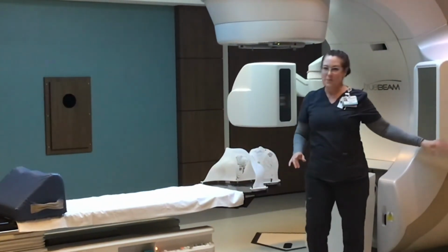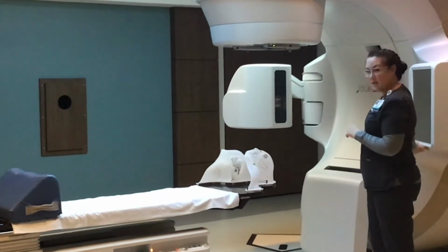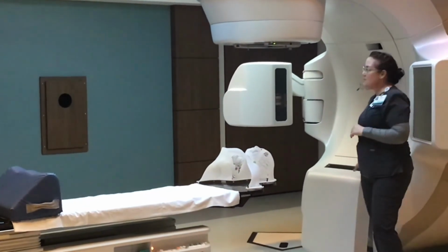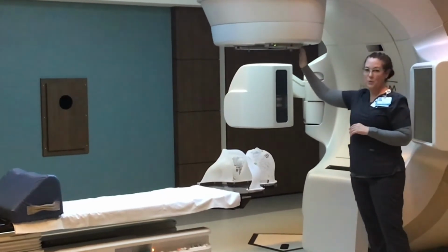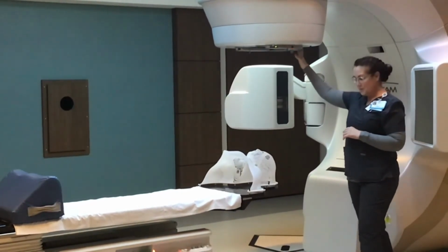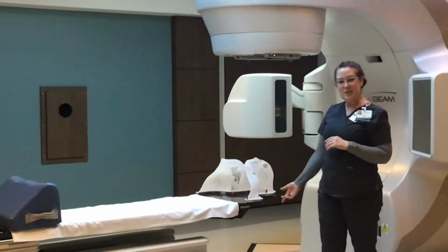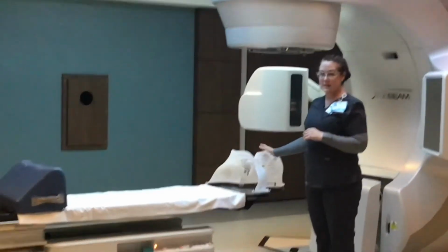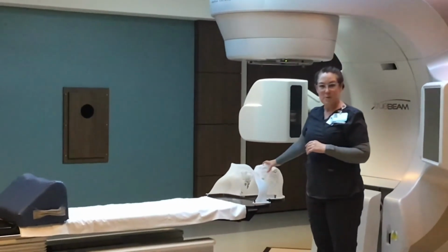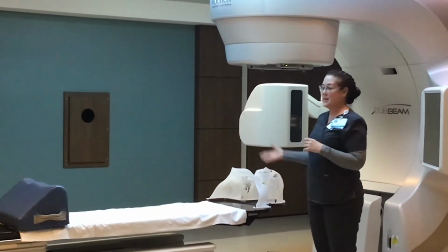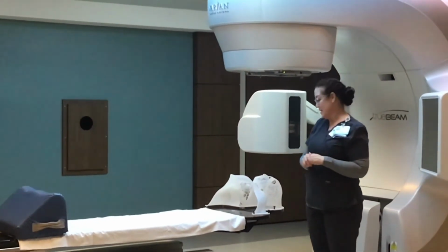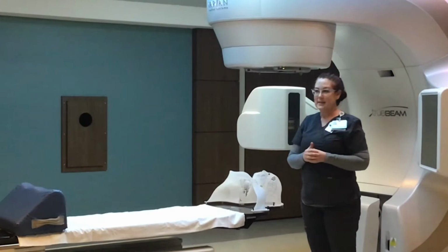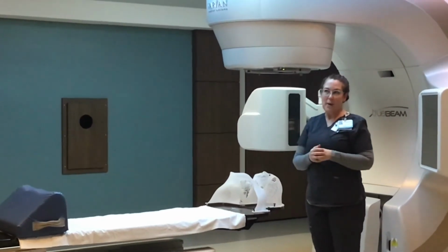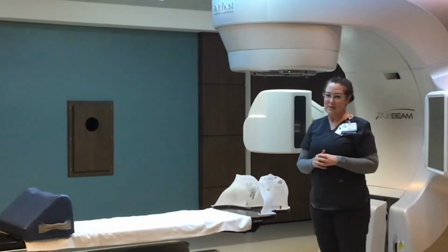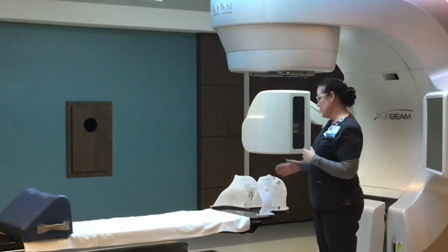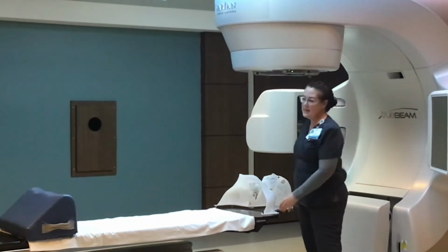We have two different imaging devices. We can do a kilovoltage, a kV image, or we can do an MV image with the actual radiation that we would deliver for treatments. After x-raying the patient, making sure that they are lined up where the doctor has prescribed treatment, we would then go back out to the console area and deliver the treatment. And then when that is done, it probably would take 10 to 15 minutes total. We would come back into the room, bring the patient out of their equipment and off the table.